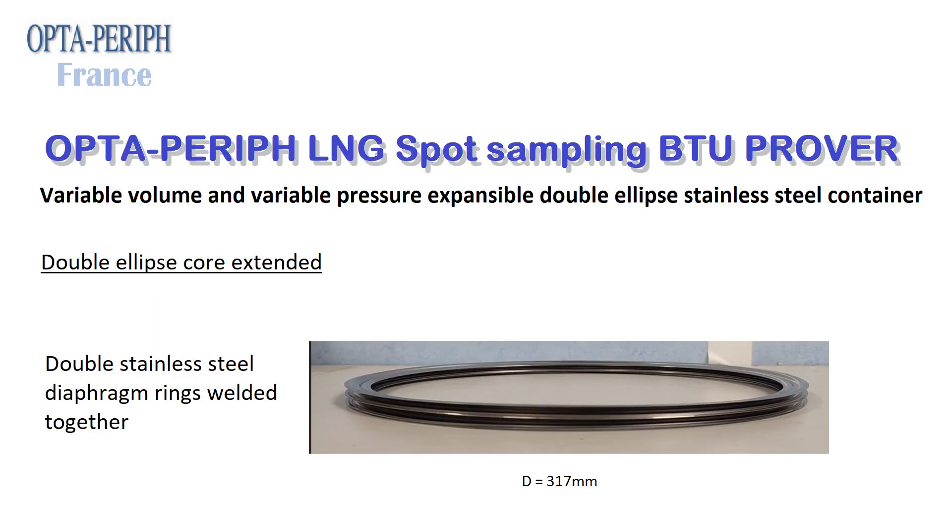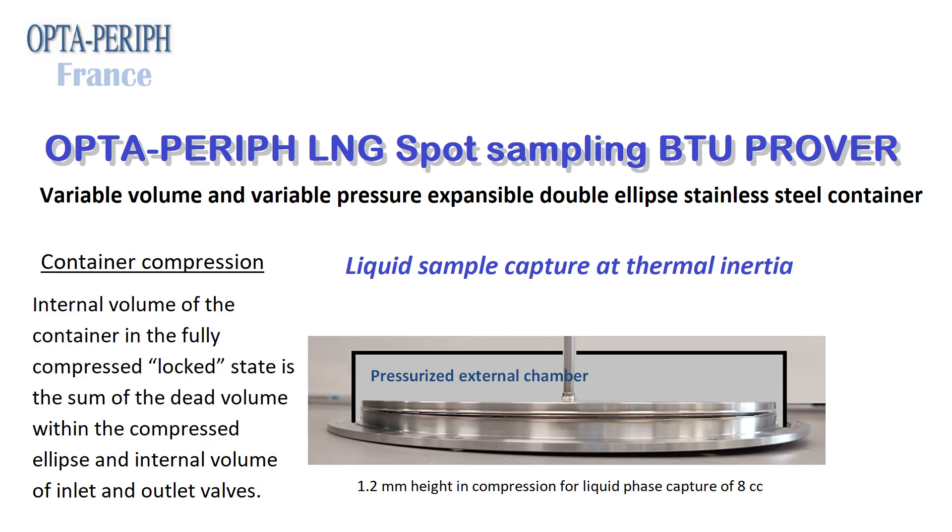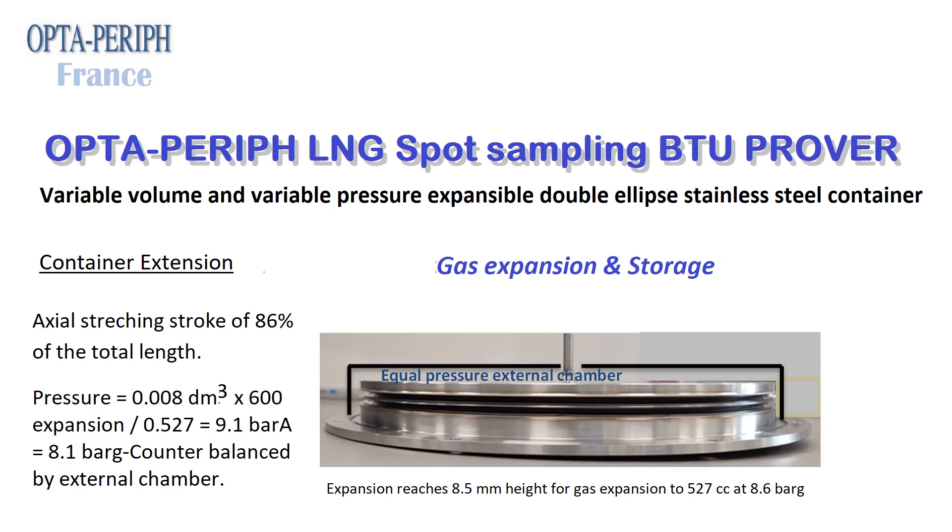Opta-Periph LNG spot sampling BTU Prover: variable volume and variable pressure expansible double-ellipse stainless steel container, double-ellipse core extended with stainless steel diaphragm rings welded together. Container compression: internal volume in the fully compressed locked state is the sum of the dead volume within the compressed ellipse and internal volume of inlet and outlet valves. Container extension — gas expansion and storage: axial stretching stroke of 86% of the total length, volume expansion 8 to 500 cubic centimeters, pressure expansion 8.1 Barg counterbalanced by external chamber.